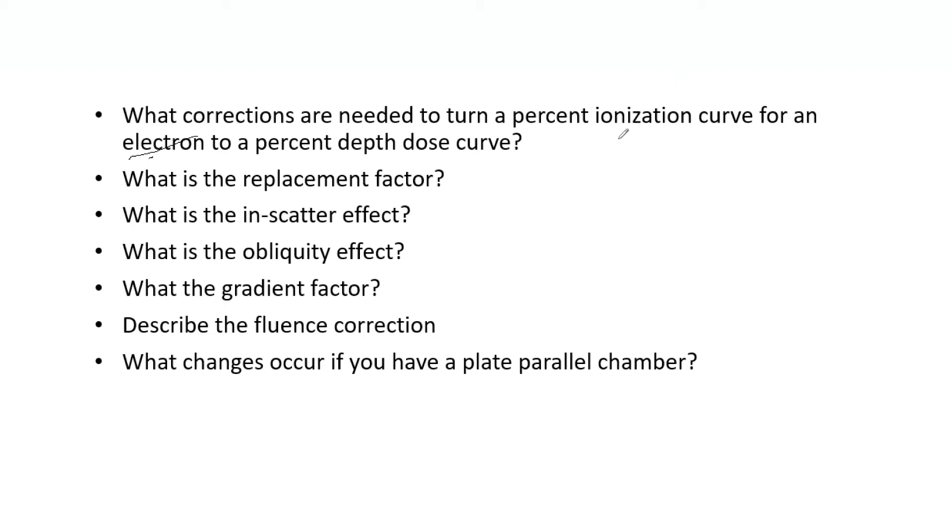To answer the first question, for an ionization chamber you have to correct for the restricted mass stopping power ratio of water to air. That is, if you remember in your studies, the L over rho, and of course that's going to be water to air. This is a function of mean energy and depth. You also need to account for the replacement factor, which we're going to cover here soon. This does differ a little bit between electrons and photons.